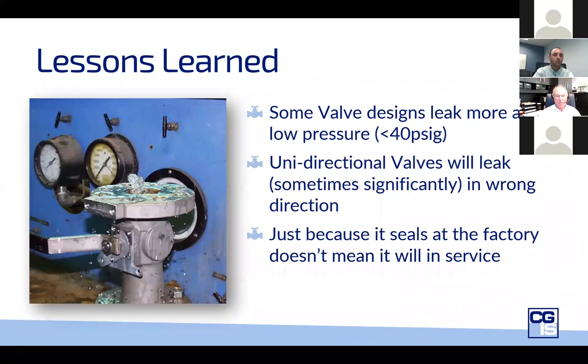We keep learning lessons as we go. I sold valves for anhydrous ammonia, which can change its volume from a liquid to a gas by 850 times. To safely do that in the system, you need to vent that gas upstream. We sold the valve and I was called because he said 'my valves are leaking on the test.' When I got to the plant where they were testing it, I actually smiled in relief, because this is doing exactly what it's meant to do — it's relieving the body cavity test. The valve was put in the wrong way. If it was put in correctly, the unidirectional way, it would be venting upstream.